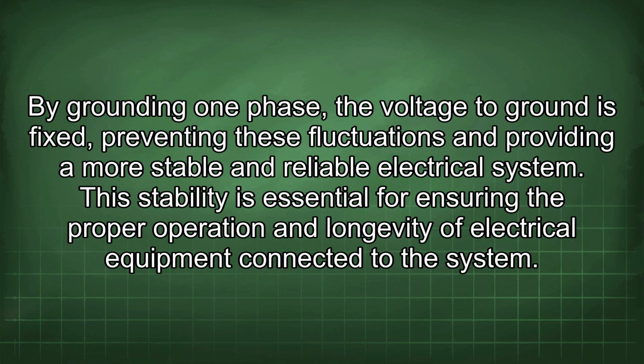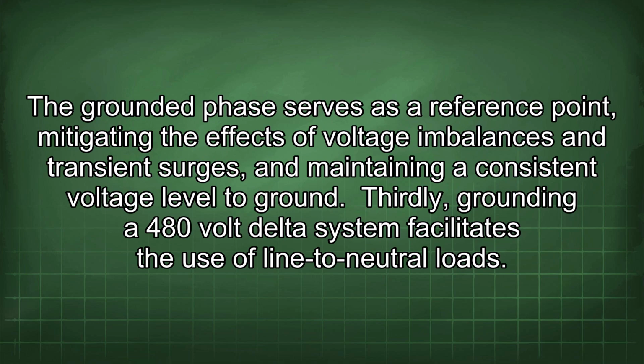By grounding one phase, the voltage to ground is fixed, preventing these fluctuations and providing a more stable and reliable electrical system. This stability is essential for ensuring the proper operation and longevity of electrical equipment connected to the system. The grounded phase serves as a reference point, mitigating the effects of voltage imbalances and transient surges, and maintaining a consistent voltage level to ground.